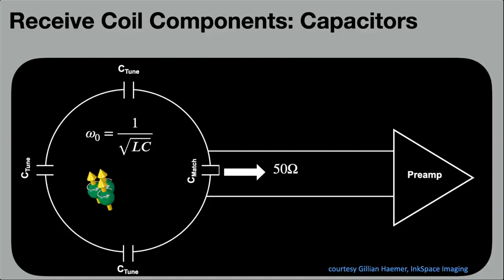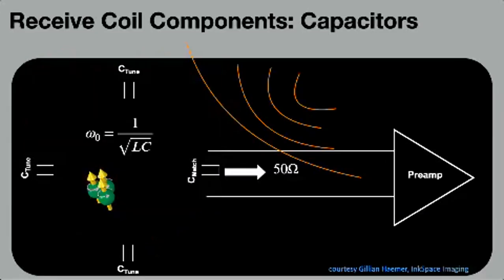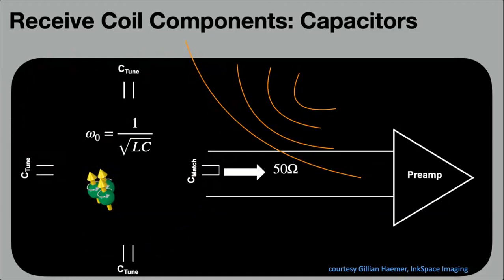However, in this configuration, during transmit—so this is just the receive coil, and now you're going to be transmitting RF while this is at resonance—the receive coil will also capture the immense transmit energy. This poses severe risk to the equipment and the patients. Because if you think about it, if you want to maximize sensitivity at the Larmor frequency, and if you transmit at the same time, then you'd get a huge amount of current within the coil. So that's a huge problem, and that's because the coil is designed to be receive only.